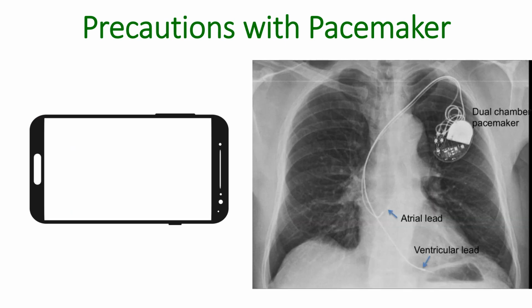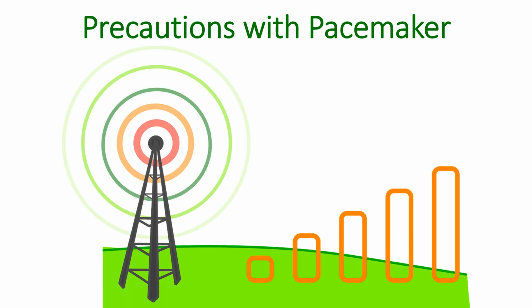But now probably the most common electromagnetic equipment which we use is a mobile phone. While using a mobile phone, keep it as far away from the pacemaker site as possible, at least 15 cm, typically in the opposite ear. If the pacemaker pulse generator has been implanted below the left clavicle, use the mobile phone in the right ear. Of course, a person with a pacemaker should keep away from mobile towers as the signal strength there is very much higher than that from a mobile phone. But this is not usually a problem as the towers are usually located high up.